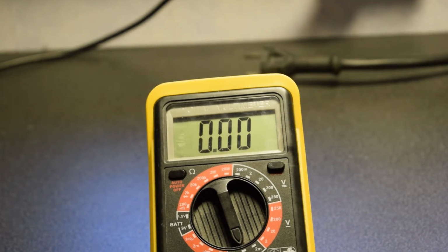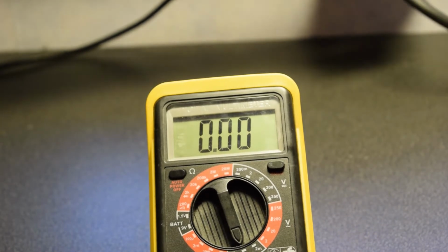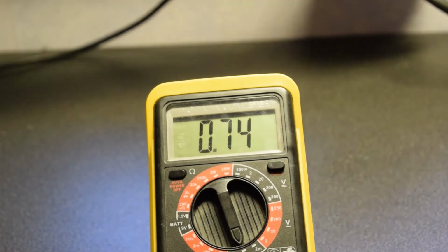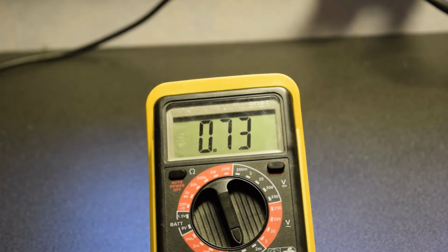Okay, I've connected the ballast without any load. Let's see how much we get. Without the load we get about 0.74 amps. So as you see, the ballast is actually doing a pretty good job at limiting how much current this thing draws. Now, let's short it out. And we get about 3 amps. This is a continuous short across the secondary, basically. So 3 amps on the primary at full load, that's not too bad.